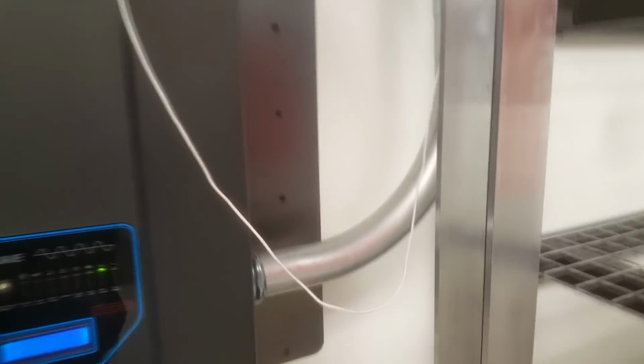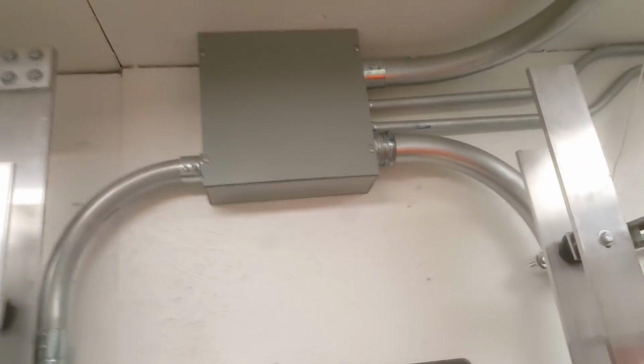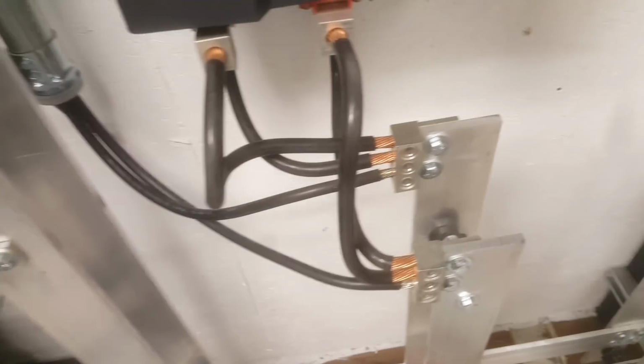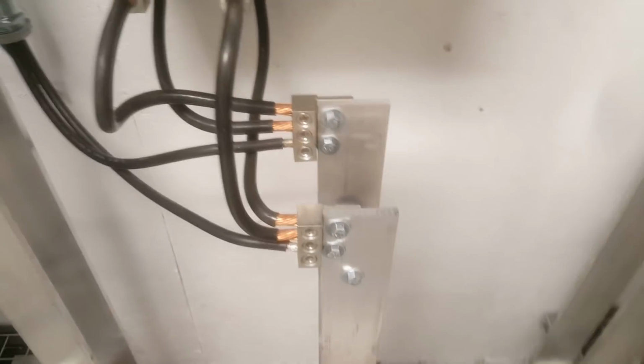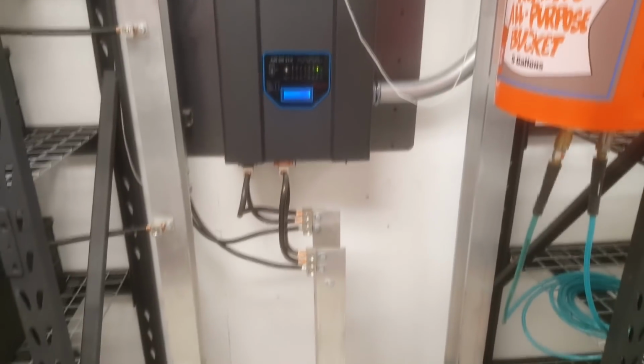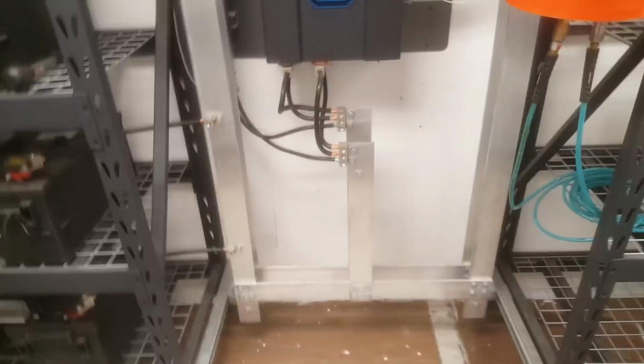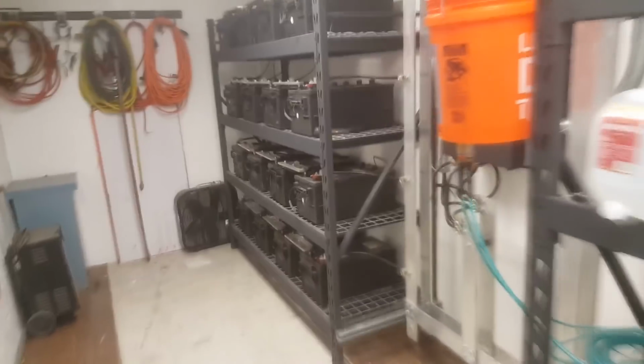The input for the charger and output of the inverter comes through this 2-inch EMT conduit to this pull box, and then I have another conduit coming down, which is my 2-gauge aluminum wire, and that is used to bring the solar power to the batteries.